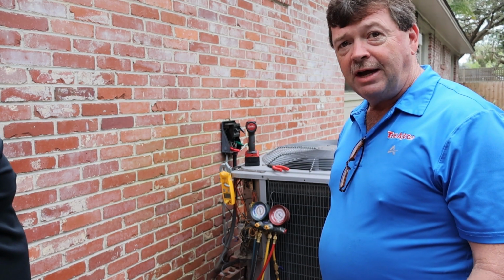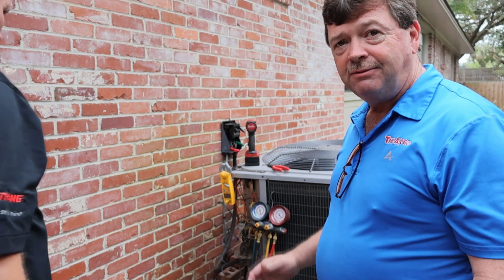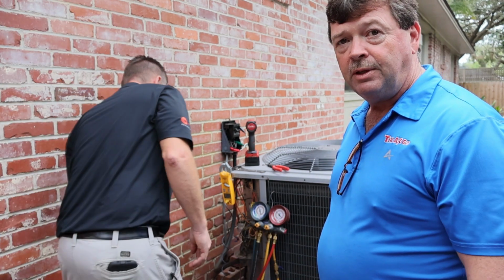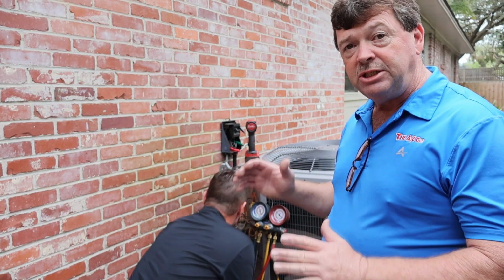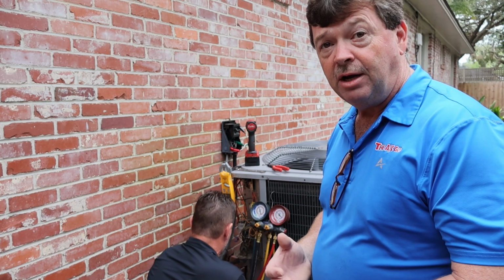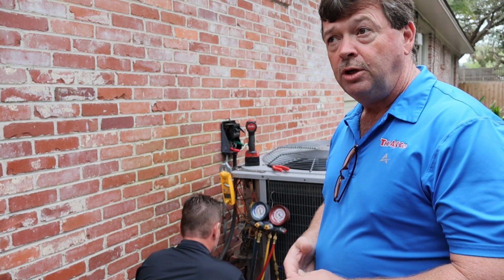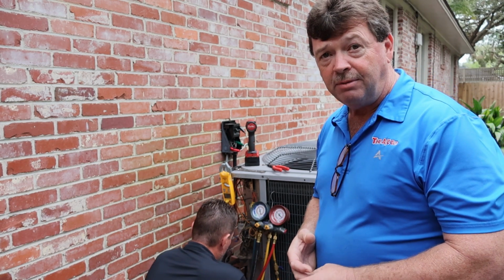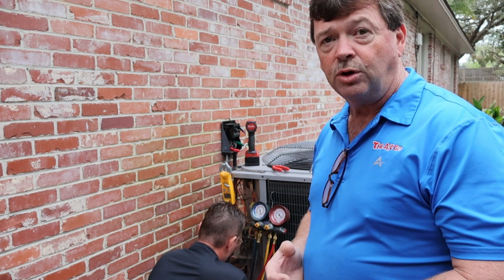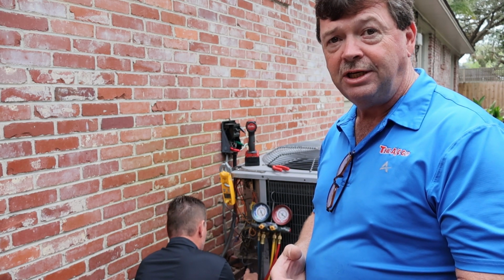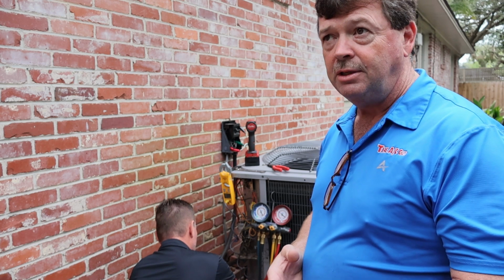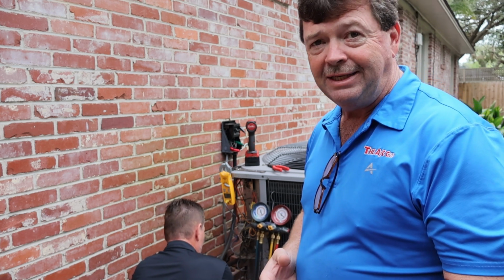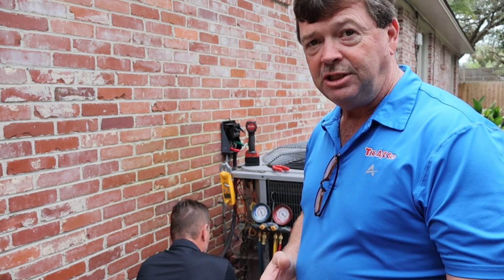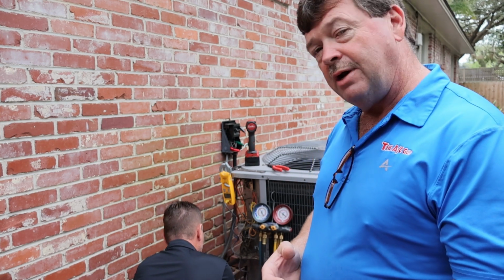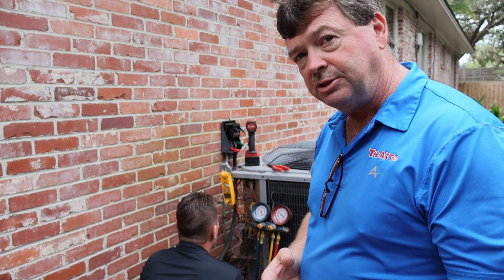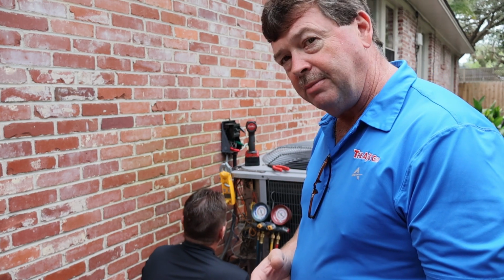Normally, most manufacturers want to see anywhere from 8 to 15 degrees superheat. If it's much above that, you could have a Freon problem. It may be low. You could have a valve that meters refrigerant into that indoor coil that could be malfunctioning and not metering Freon properly. So it really gives us a lot of insight into how this machine's performing. So he's going to have that information for us here shortly, and we'll be able to make a determination.